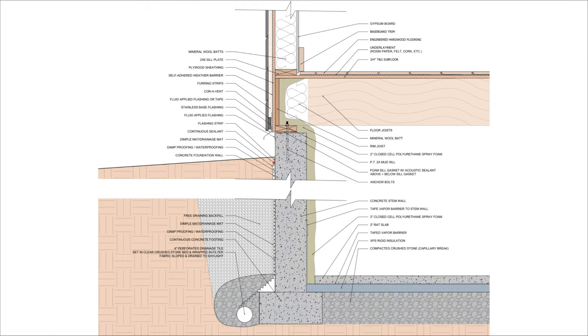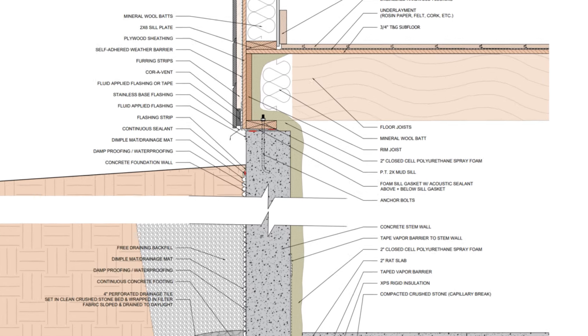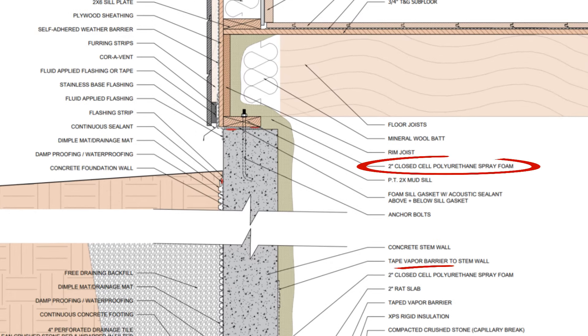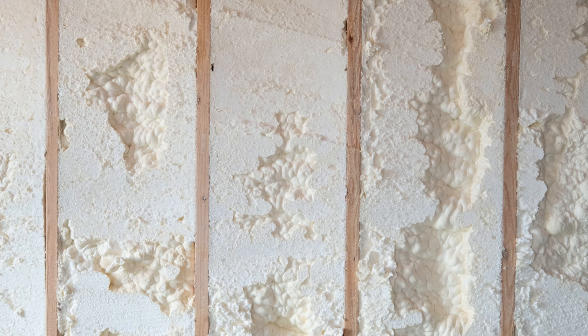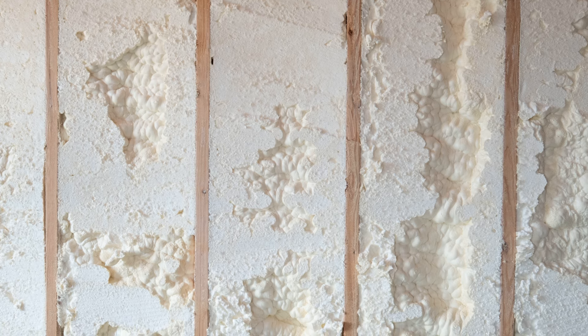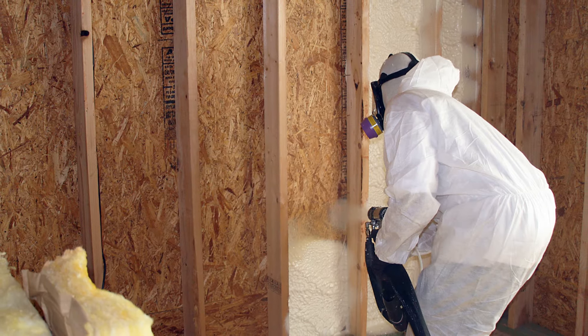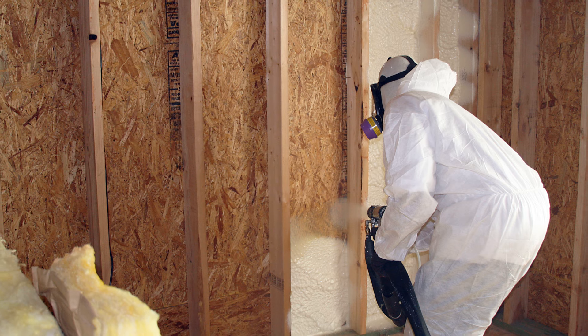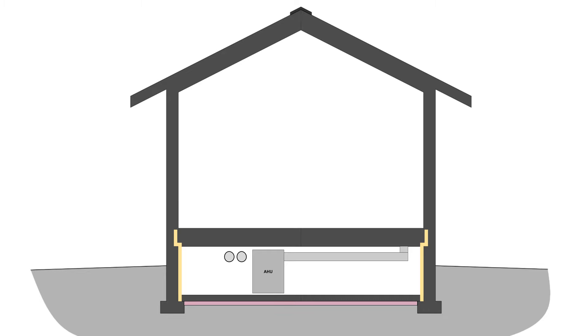Another common strategy is to apply a continuous layer of closed-cell spray foam on the interior side of the stem walls, up onto the rim joist, and on the underside of the subfloor to prevent air leakage and vapor diffusion that could result in condensation. This tends to be the most convenient option as it doesn't require taping each individual rigid insulation board and sealing around each penetration at the rim joist. However, spray foam can off-gas some nasty chemicals for an extended period of time, which can be a problem especially if ductwork is running through the conditioned crawl space.